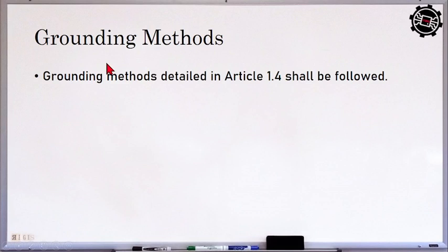Okay. So grounding methods. Grounding methods detailed in Article 1.4 shall be followed, no? So na yung grounding of all the electrical circuit, no, pertaining to outside installation, ang pinapalo talaga is yung Article 1.4, no, wherein mayroon siyang tamang bonding, no, all metal parts are connected by a wire or a conductor. Tapos continuous ang grounding, so walang putol. So yan yung pinaka-summary ng Article 1.4. So yan din yung ifa-follow when we are going to have the grounding on our underground supply lines and communication lines.